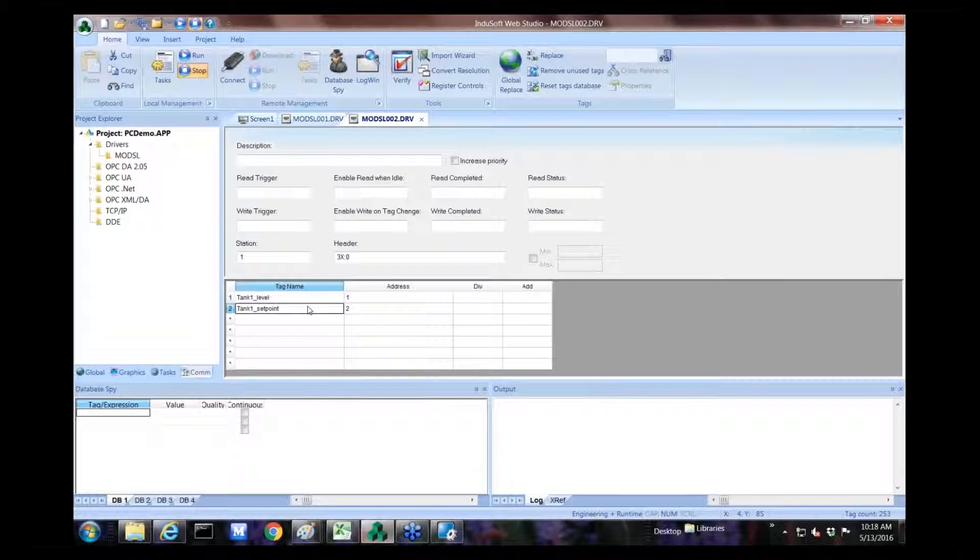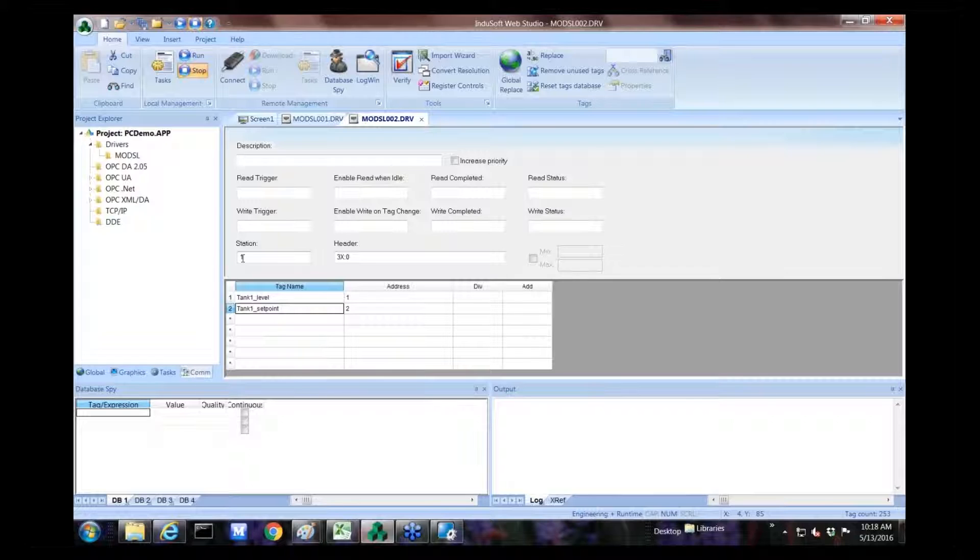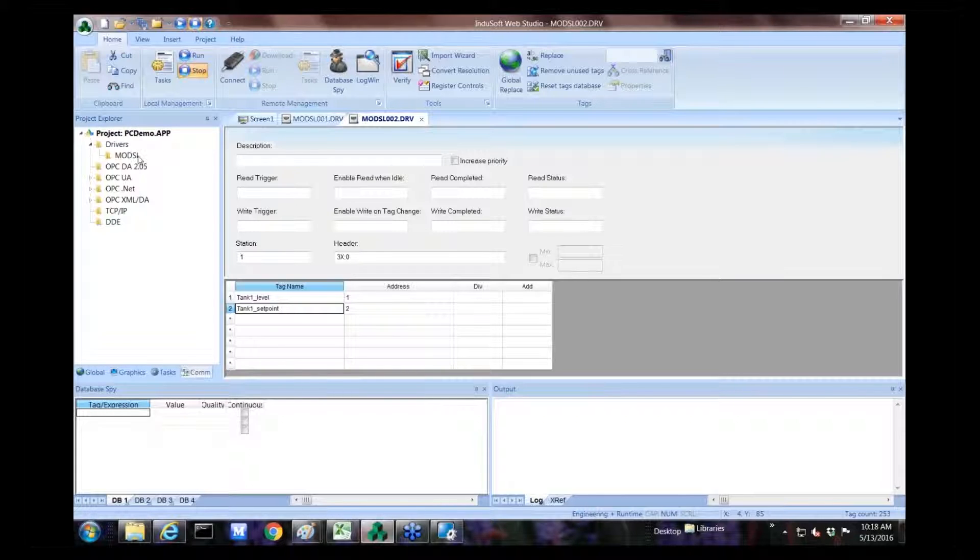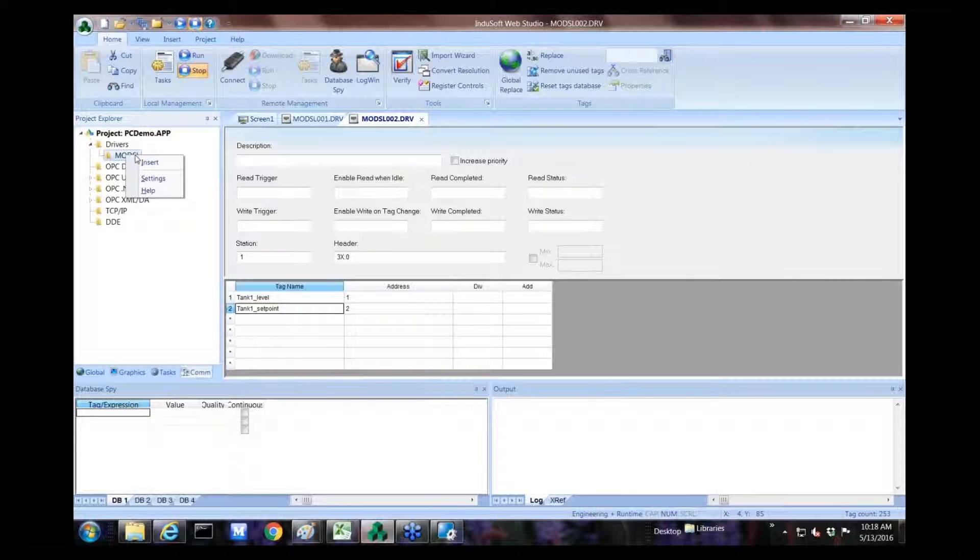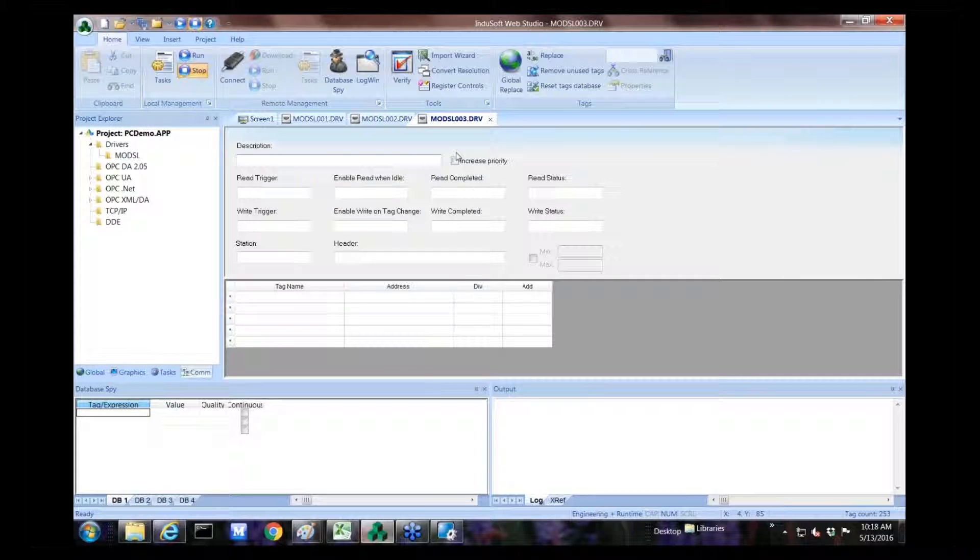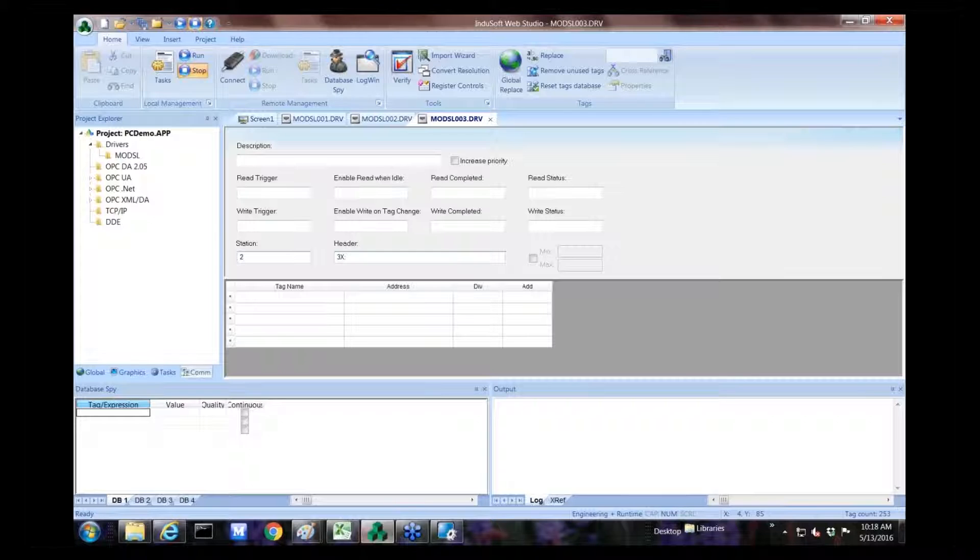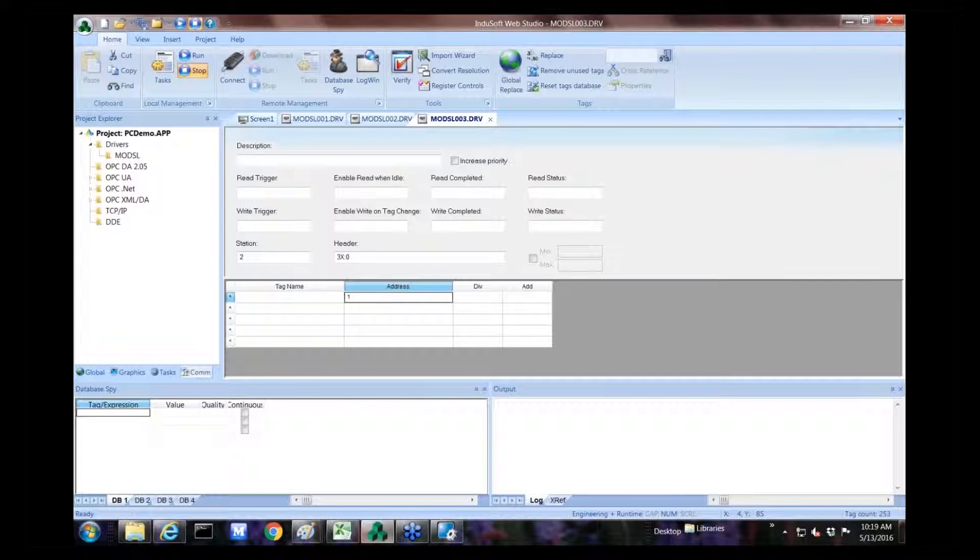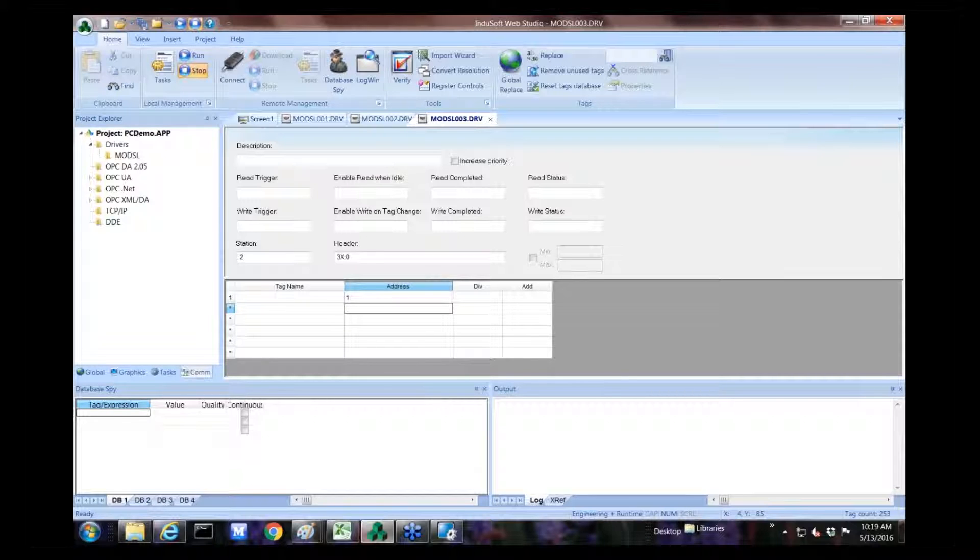To create the tags, they're Modbus devices. I've pre-created some of them. For instance, for device number one, this is a sample of what we need to do. We create two tags. First one's called tank one level. And the second one is tank one set point. And we just call it address one and address two. We create our header, which is 3x01. And our station ID of one, which is our Modbus ID for that specific device. And we just duplicate this four times. And we just do that by going here and insert.